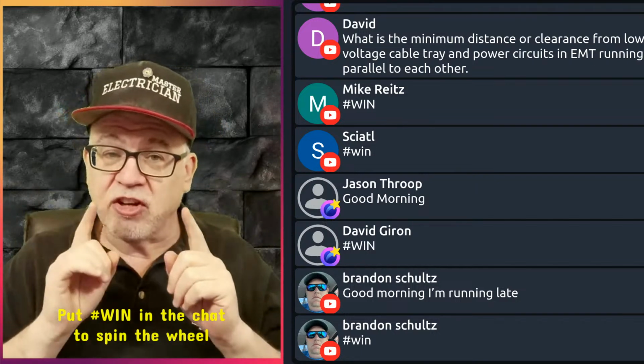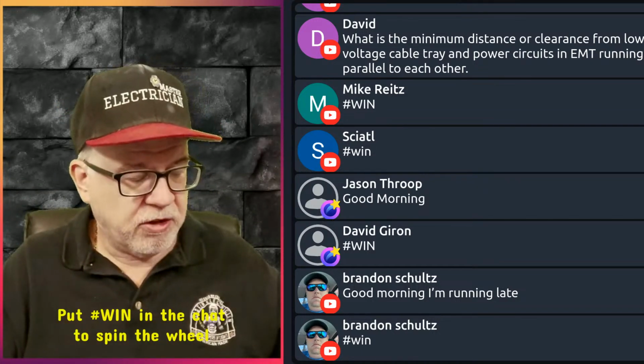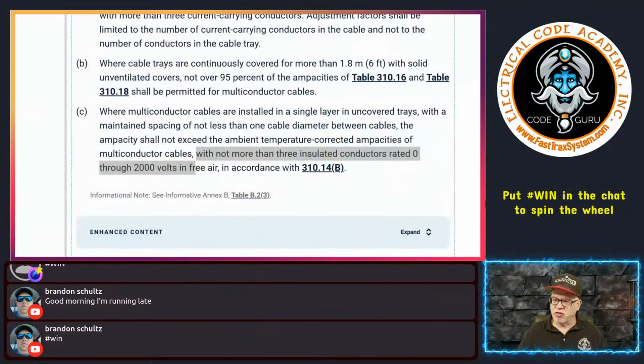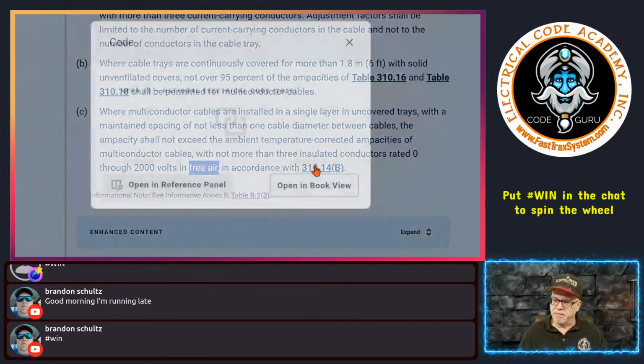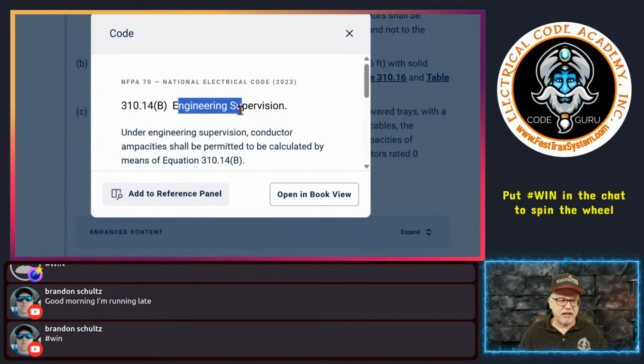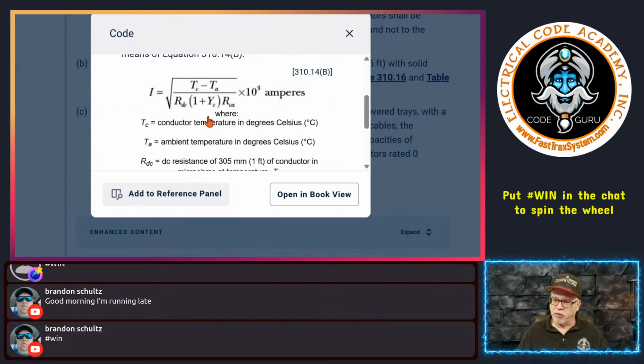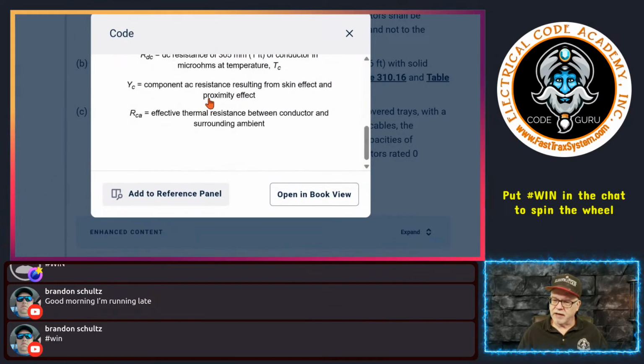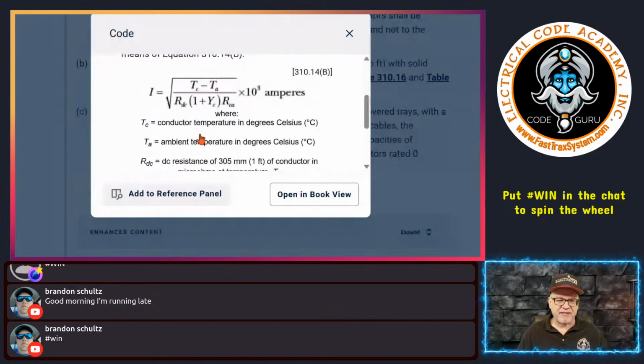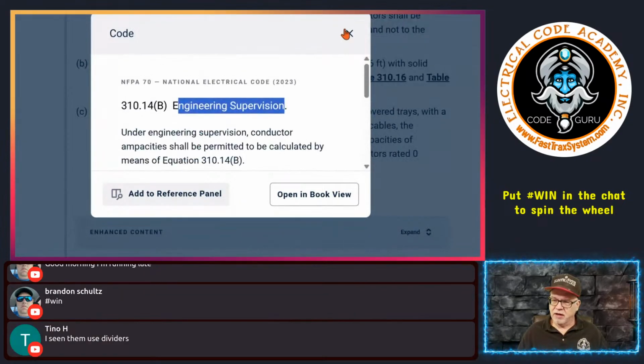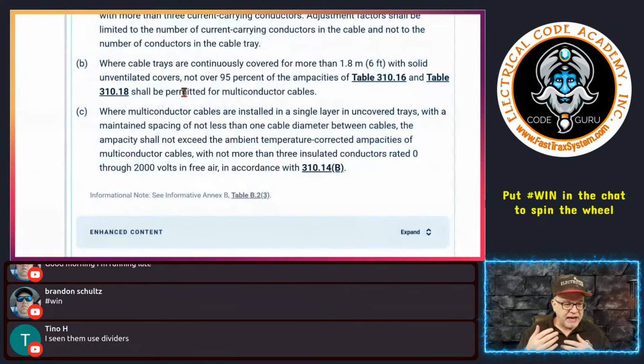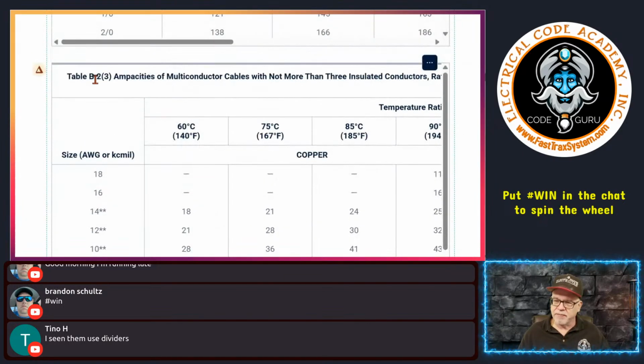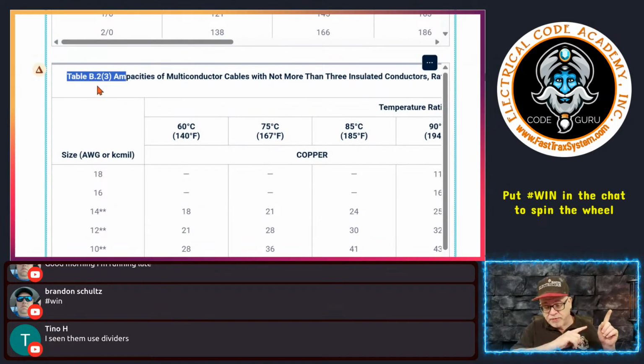Okay? But as an engineer, you do have that prerogative, right? And so when I show you this, free air doesn't mean you go use 310.17. It means, boom, it means under engineering supervision that an engineer can use this formula right here to calculate the new ampacity of this conductor, okay? Also, based on that, they can come down here and use an example that's given in the table. And I'll do this. See this table right here? This is not enforceable. This is information only.